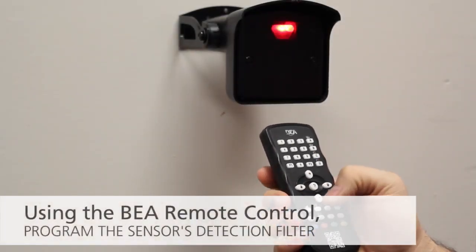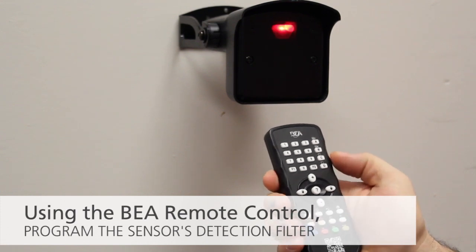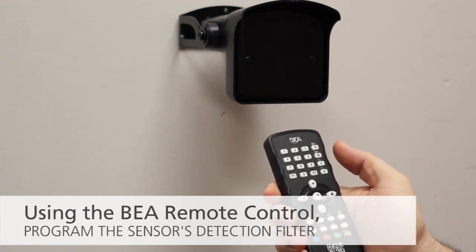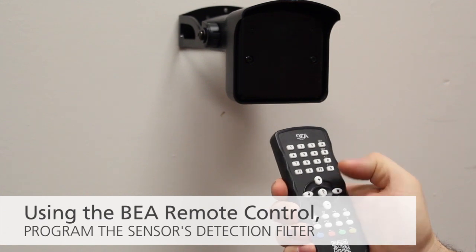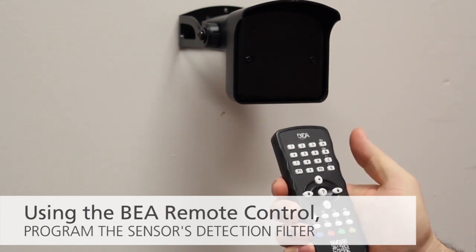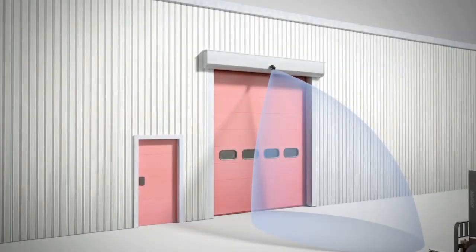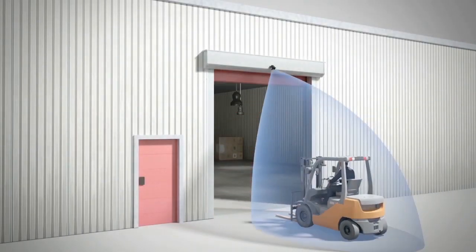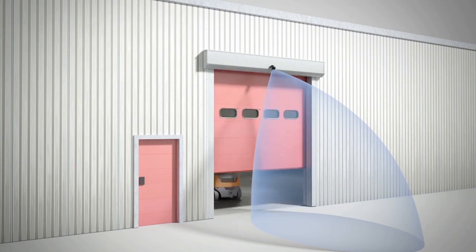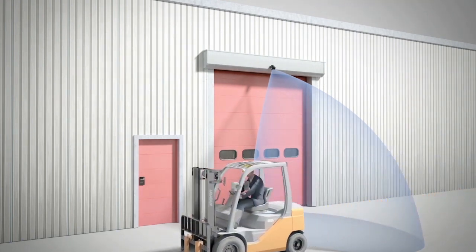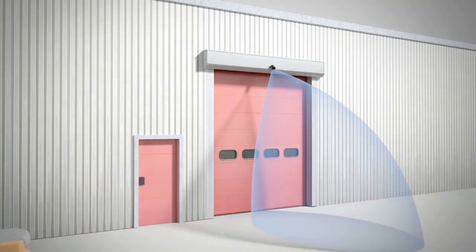Using the BEA remote control, program the sensor's rejection mode to fit the application. If a BEA remote control is not available, consult the BEA Falcon Family User's Guide for push button programming instructions. If detection of all traffic including pedestrian and cross traffic is desired, use settings 1 or 2. If pedestrian and cross traffic rejection are desired, settings 3 through 6 are recommended based on tilt angle and mounting height.